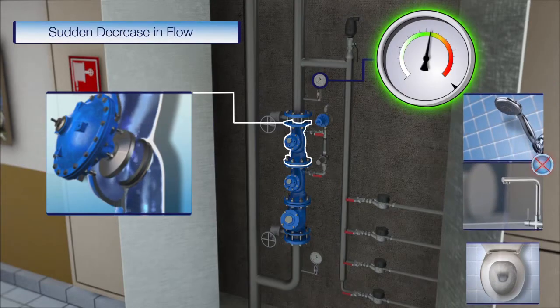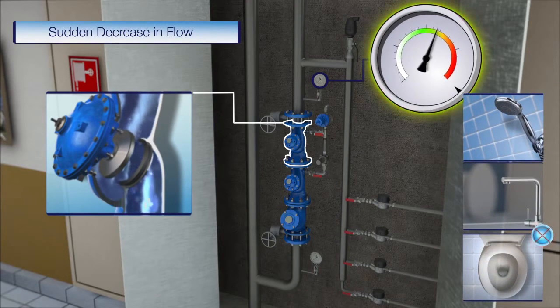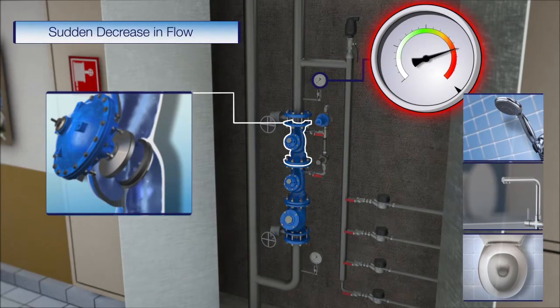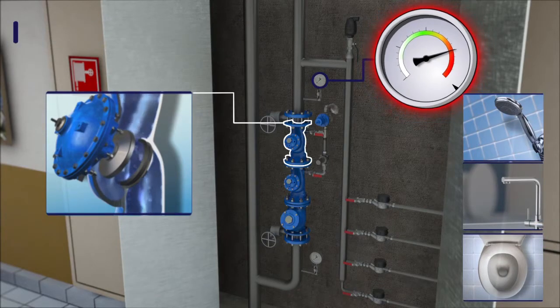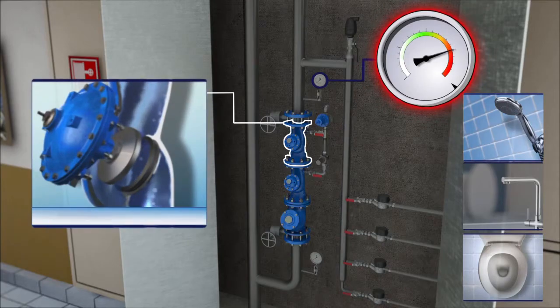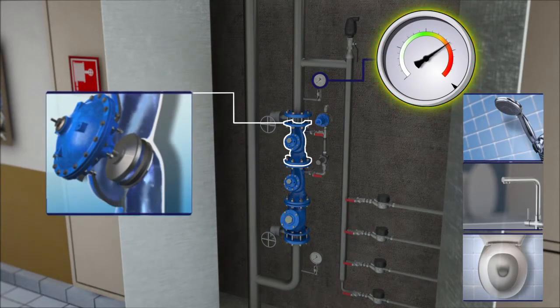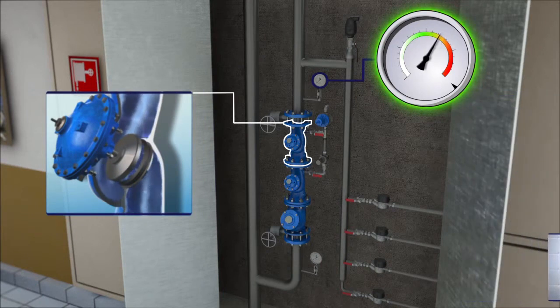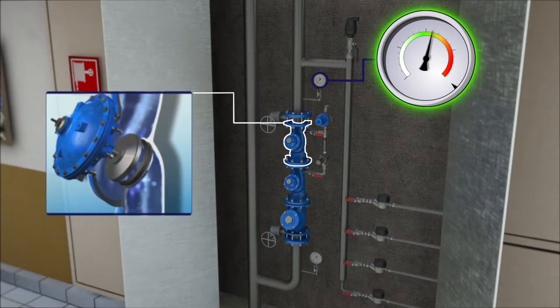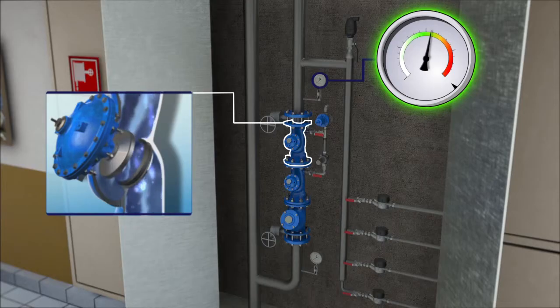When the demand for water suddenly drops, the downstream pressure rapidly rises beyond its safe setting. The emergency pressure relief valve opens its vent port for a short period, causing immediate reduction of the downstream pressure. The PRV regulates to its closed position, reduces the downstream pressure, and the system returns to safe operation setting.